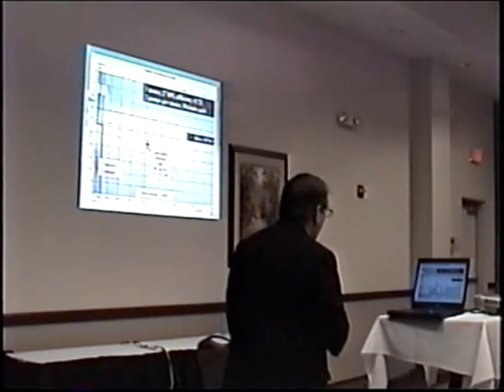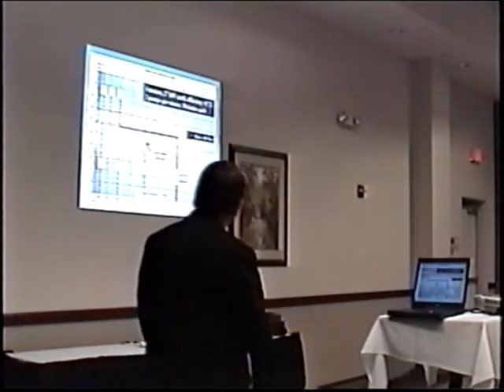Let's look at the hydraulic multiple pump system. Positive displacement pump curves: if you have one motor with its 2 pumps, you get about 100 liters per minute. So there's one motor, one pump, and we have a demand out here. We need 2 motors and 4 pumps, 3 motors and 6 pumps, or 4 motors and 8 pumps to get up to the point where we're beyond our operating point. That's how we figured out we needed 4 motors, 27 kilowatts. We knew the pressure we needed, and this line here, H max, is 115 bar.